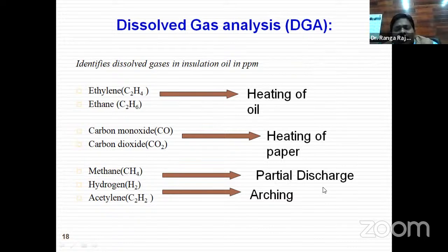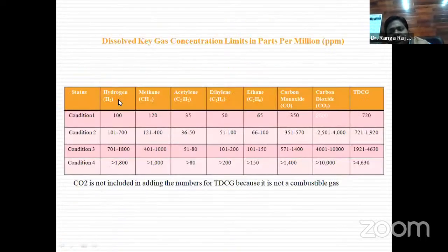Similarly, partial discharges are like arcing or sparks. The same thing that happens in outdoor overhead transmission lines also happens between the various electrical parts of the machine. Even in oil, we find voids formed due to water bubbles, and those voids lead to partial discharges, which can further develop into arcing. During arcing, we find hydrogen and acetylene gases, while at the partial discharge level we find methane and hydrogen. So we can detect all these conditions through oil analysis, the DGA test.